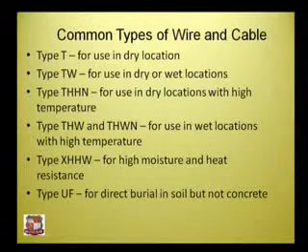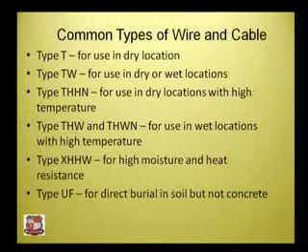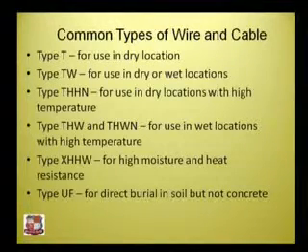If it is written as THW and THWN, it is used in wet locations with high temperature. If it is written as XHHW, it is for high moisture and heat resistance. So depending on your environment, your moisture content, and your heat conditions, we should go for these cables. If it is UF, it is for direct burial in soil but not concrete.